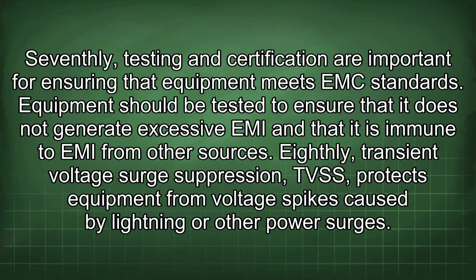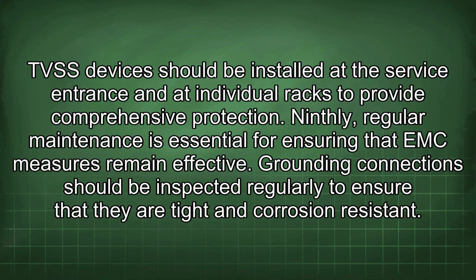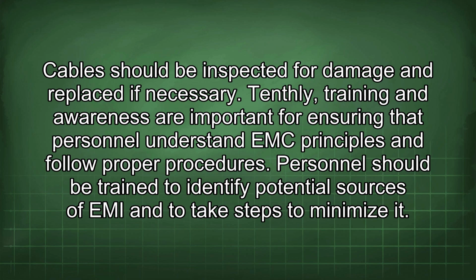from other sources. Eighthly, transient voltage surge suppression (TVSS) protects equipment from voltage spikes caused by lightning or other power surges. TVSS devices should be installed at the service entrance and at individual racks to provide comprehensive protection. Ninthly, regular maintenance is essential for ensuring that EMC measures remain effective. Grounding connections should be inspected regularly to ensure that they are tight and corrosion resistant. Cables should be inspected for damage and replaced if necessary.